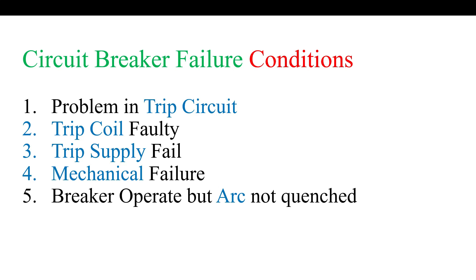The third failure condition is trip supply failure — if the tripping supply fails, meaning no supply is available, then our trip coil and circuit breaker will not operate. This is also a circuit breaker failure and the CBF relay will operate. The fourth failure condition is mechanical failure — if everything electrical, including the trip coil, DC supply, and trip circuit, is healthy but due to a mechanical or mechanism failure the circuit breaker does not operate, the CBF relay will also operate.